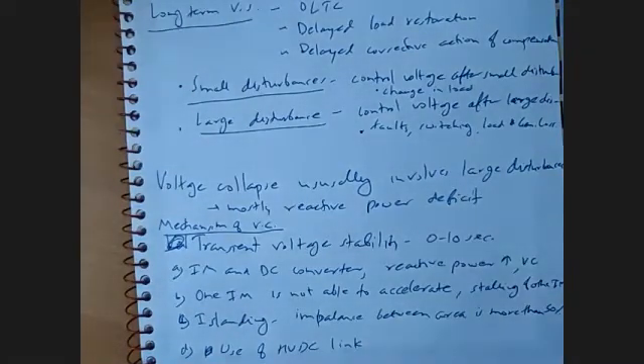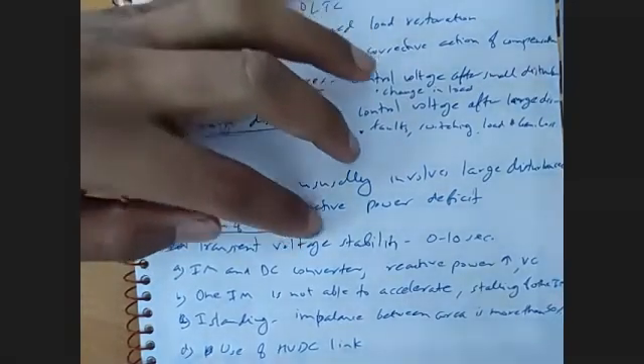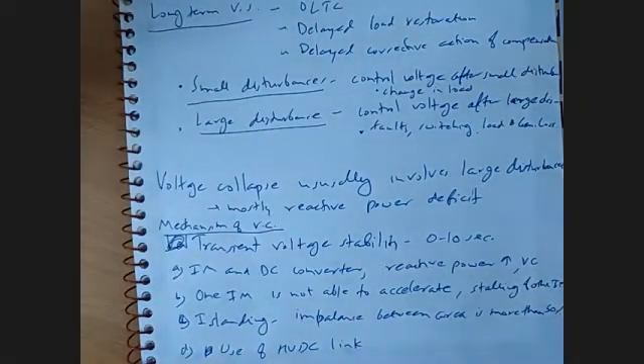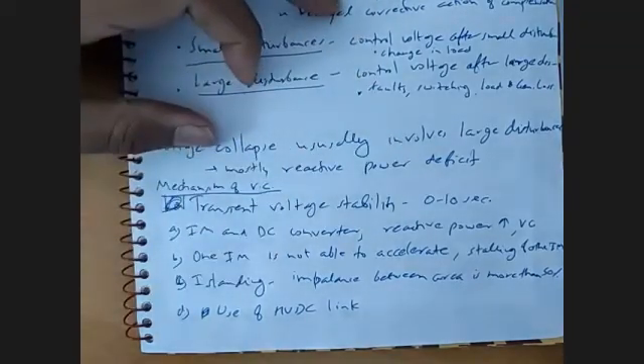When we are talking about voltage collapse, we have transient voltage stability and steady state voltage stability. Transient voltage stability is about the system being stable for a very small duration, almost 0 to 10 seconds. If the system is able to become stable within 10 seconds of the disturbance, then that comes under transient voltage stability. Transient voltage instability can be due to various issues. The major issue is due to induction motor and DC converter operation.